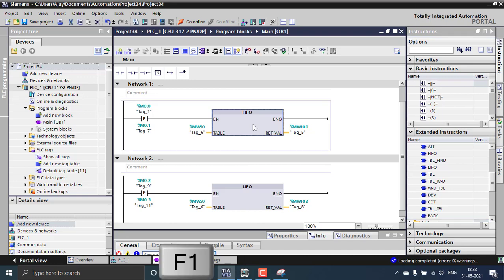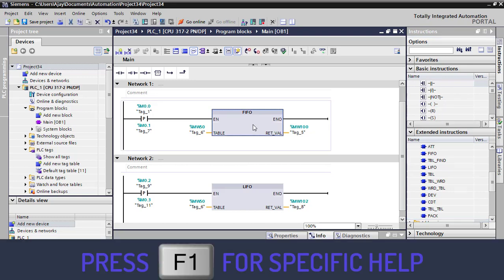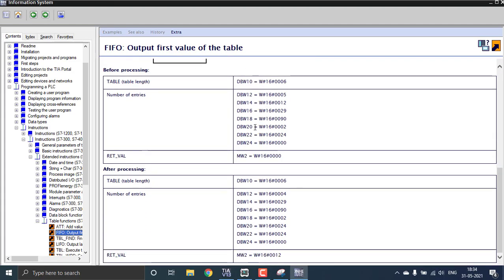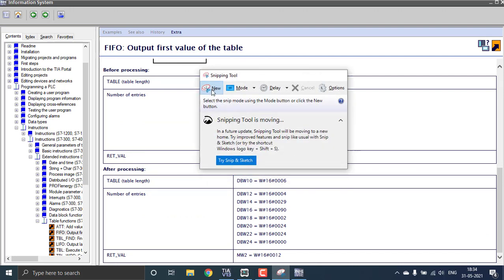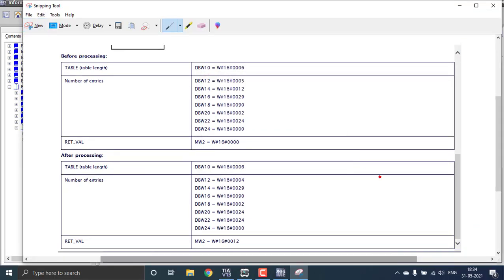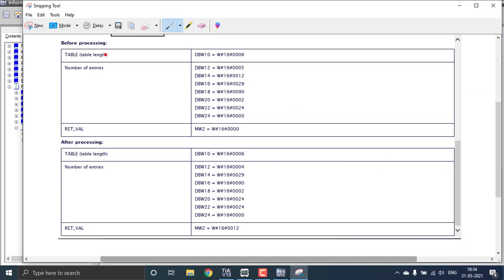Let's go to the help for the FIFO first. I'm selecting the FIFO block and pressing F1 on my keyboard to get the corresponding help. Looking at the help, before processing, this will be the table. The first element or starting address stands for the length of the table, which is mentioned as six — so that contains six elements. In our data, MW50 will be considered as six, the number of elements.